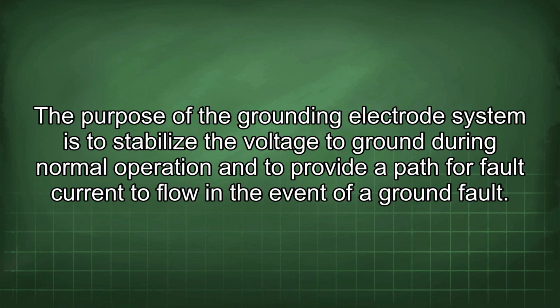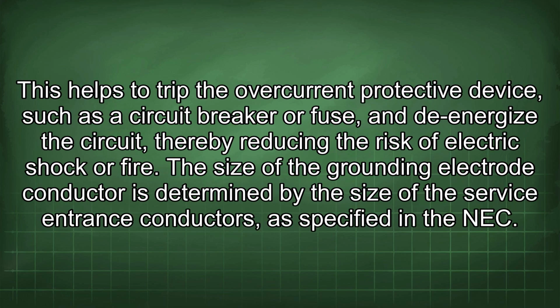The purpose of the grounding electrode system is to stabilize the voltage to ground during normal operation and to provide a path for fault current to flow in the event of a ground fault. This helps to trip the overcurrent protective device, such as a circuit breaker or fuse, and to de-energize the circuit, thereby reducing the risk of electric shock or fire.